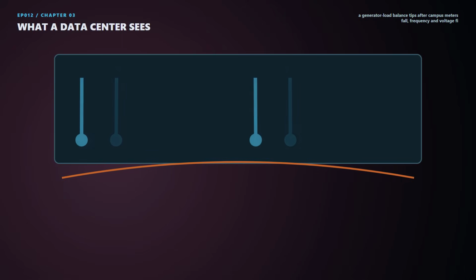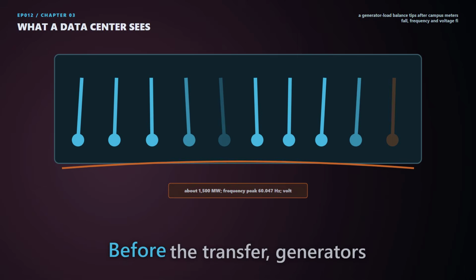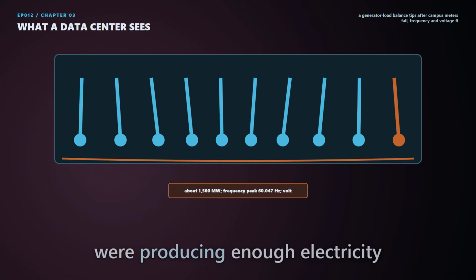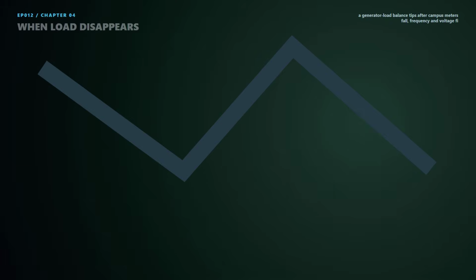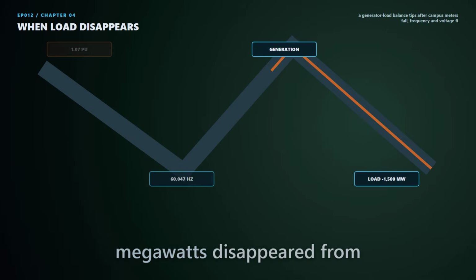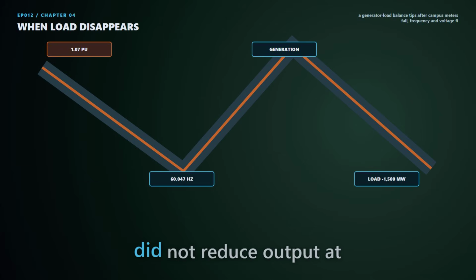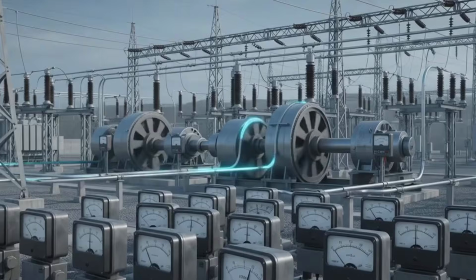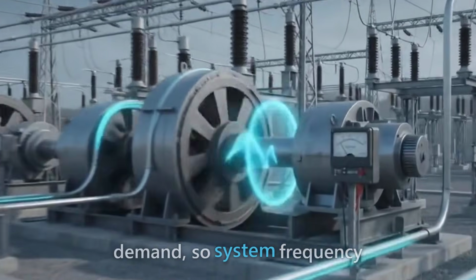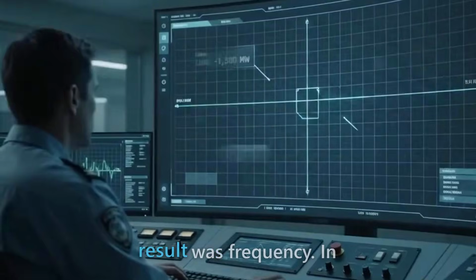Power systems have to balance generation and demand continuously. Before the transfer, generators were producing enough electricity to meet the load. When approximately 1,500 megawatts disappeared from the grid, those generators did not reduce output at the same instant. For a moment, supply exceeded demand, so system frequency rose. The first visible result was frequency.